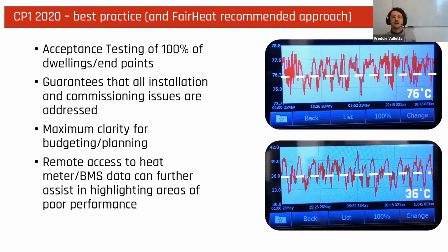Whilst you may be thinking that 100% of testing seems a bit overkill and could impact on project timelines, it's actually the best approach to take, not just in terms of the results that it produces, but in terms of being able to budget and plan for this commissioning and testing phase of the works without any unknowns. The 10% plus 10% minimum requirement approach stipulates that if any of those fail, a whole new set of 10% has to be tested and passed in order to prove correct commissioning. And then another 10% if any fail, another 10% if any of those fail, and so on. This introduces quite a lot of unknowns into project planning and budgeting.